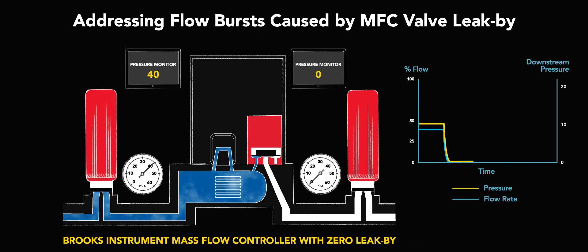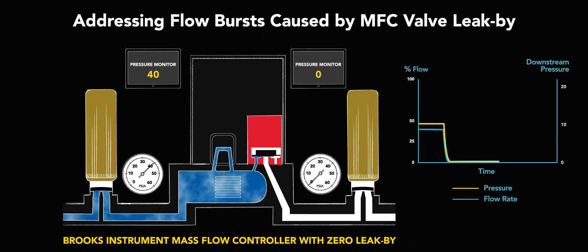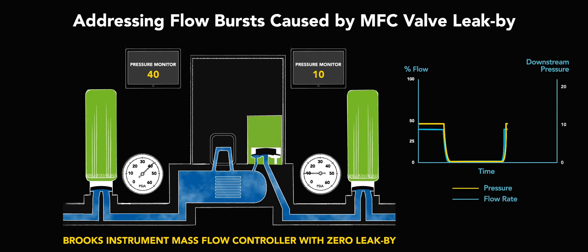With 40 PSIA between the upstream and downstream isolation valves, our zero leak-by valve technology reduces cross-seat leak-by over 100x. During the first process setpoint, the pneumatic isolation valves are open along with the MFC valve. All valves are open, and gas is flowing at a steady rate.